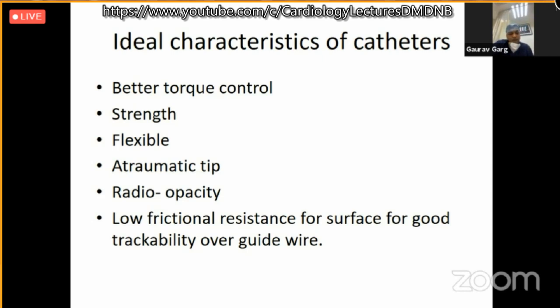It should have good memory — meaning it should remember its shape. Whenever we pass the catheter inside a sheath and it comes out, it should regain its original shape. The friction of the catheter from surfaces such as the guidewire or vessel wall should be very low; it should not rub against them.